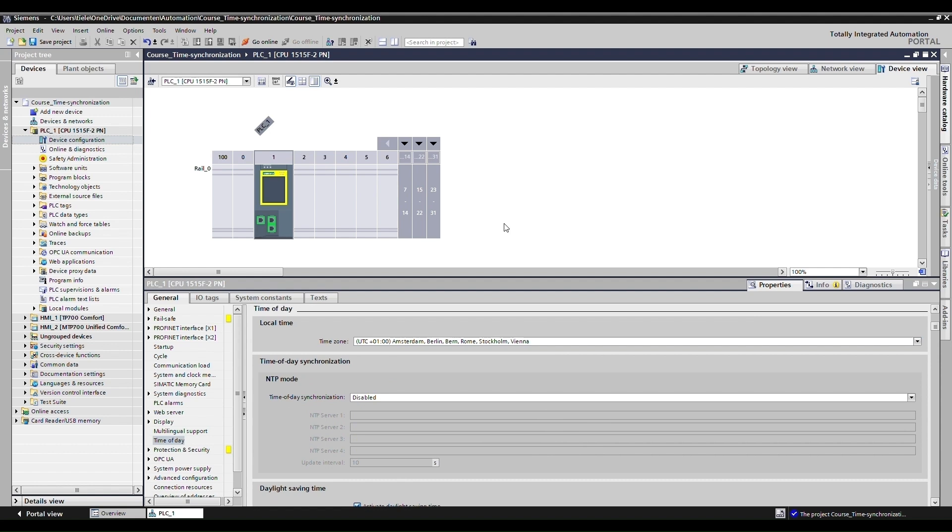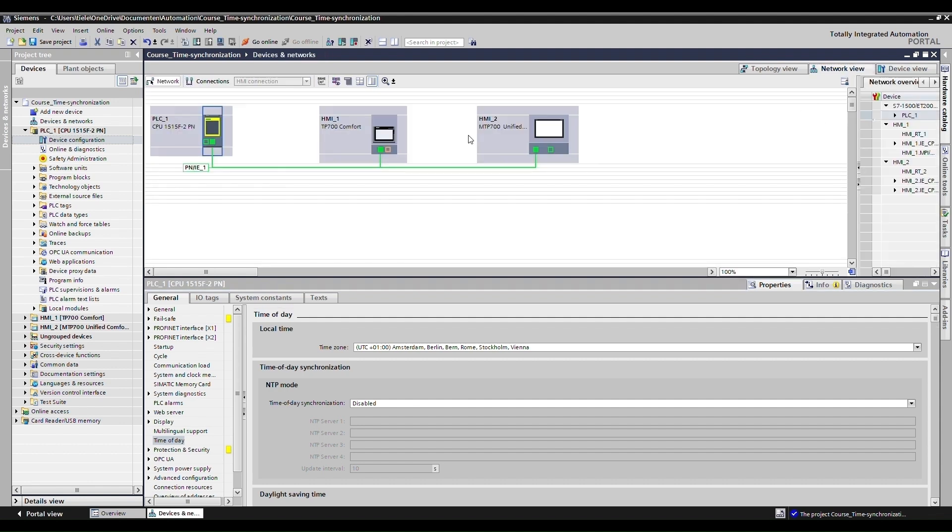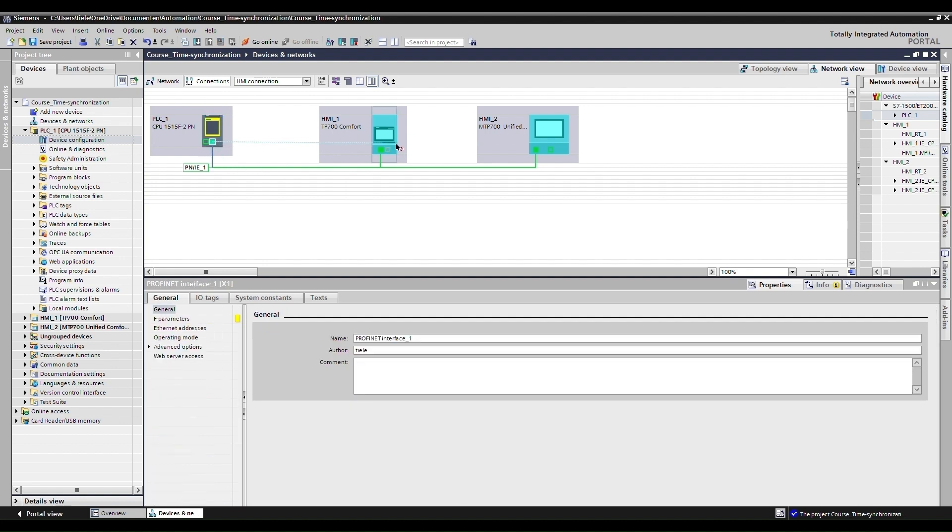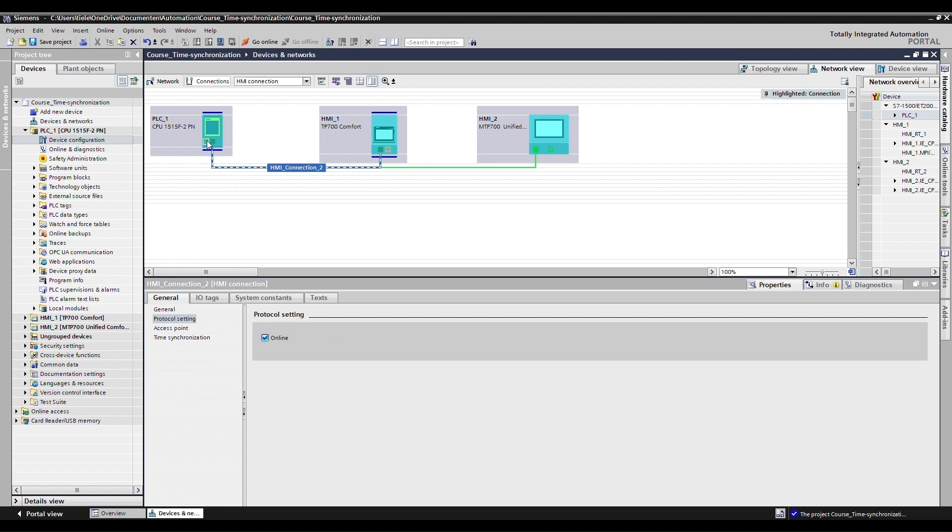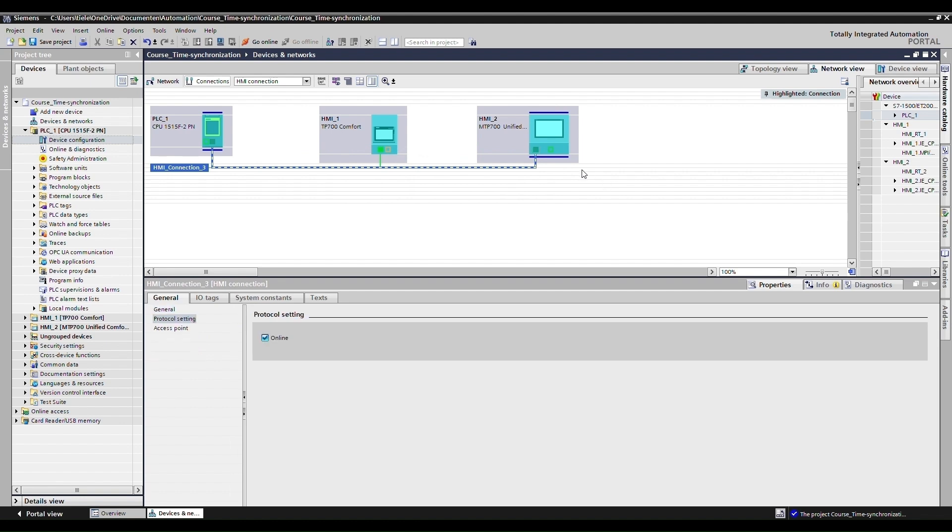So first of all, when we have now configured the PLC, we want to synchronize the time with the HMI. Since we want to have one single source of truth for the date and time. And that's why we will first have a look at the comfort panel. So to synchronize these times for the comfort panel, all we need to do is adjust the connection to it. So as you might see, there's no HMI connection just yet between the PLC and the HMI. I will do that now. Just simply dragging it. And I'll also create HMI connection to the other HMI for the unified series. Just for later on.